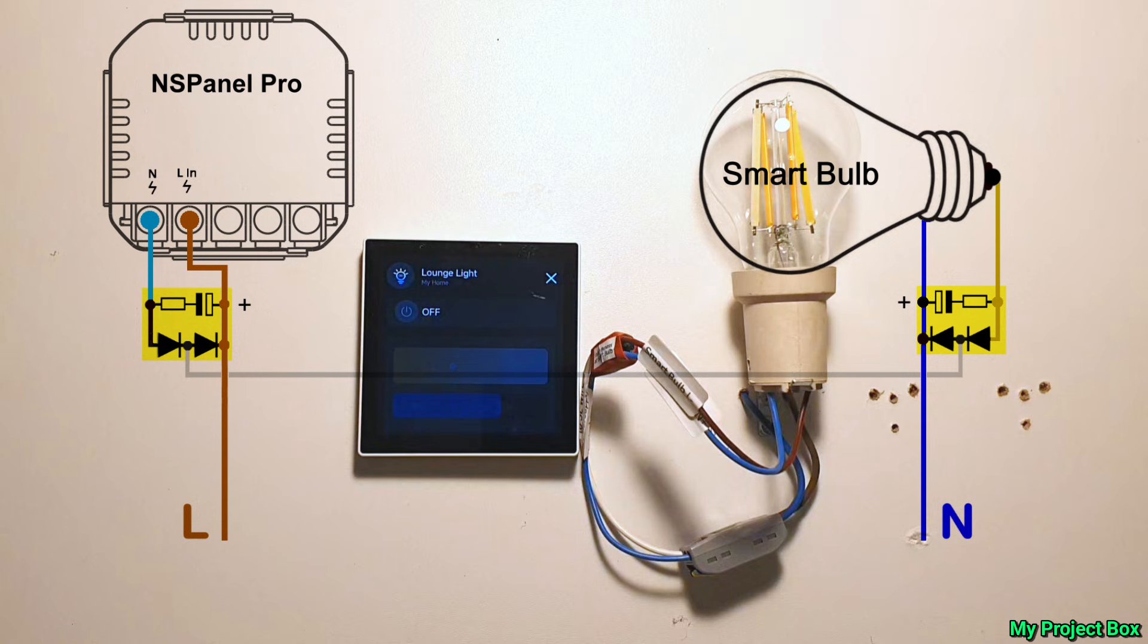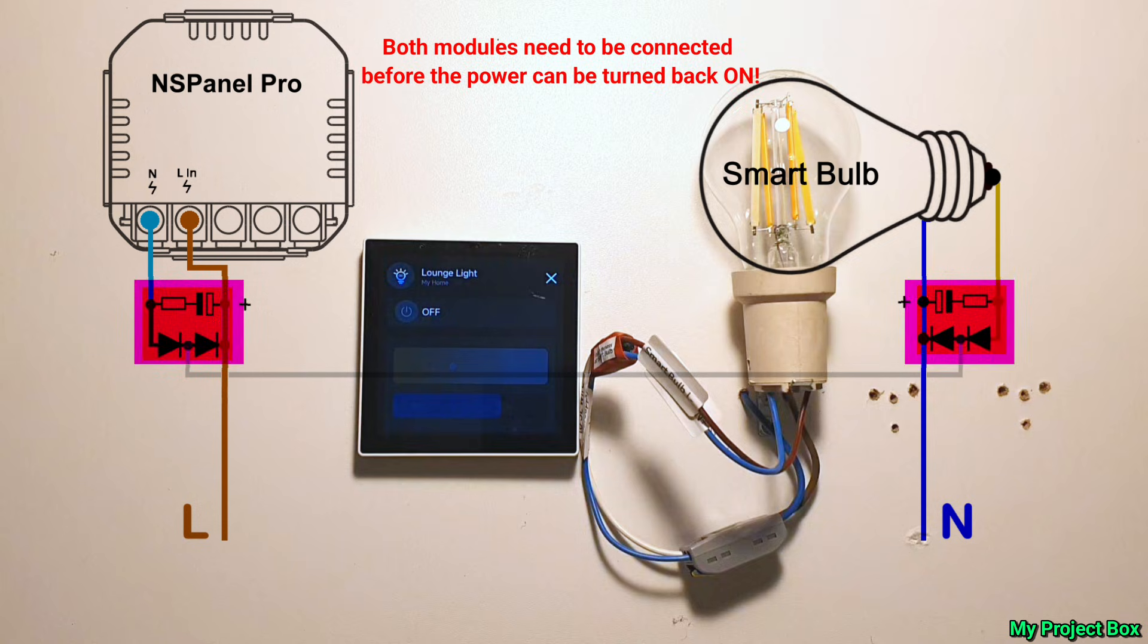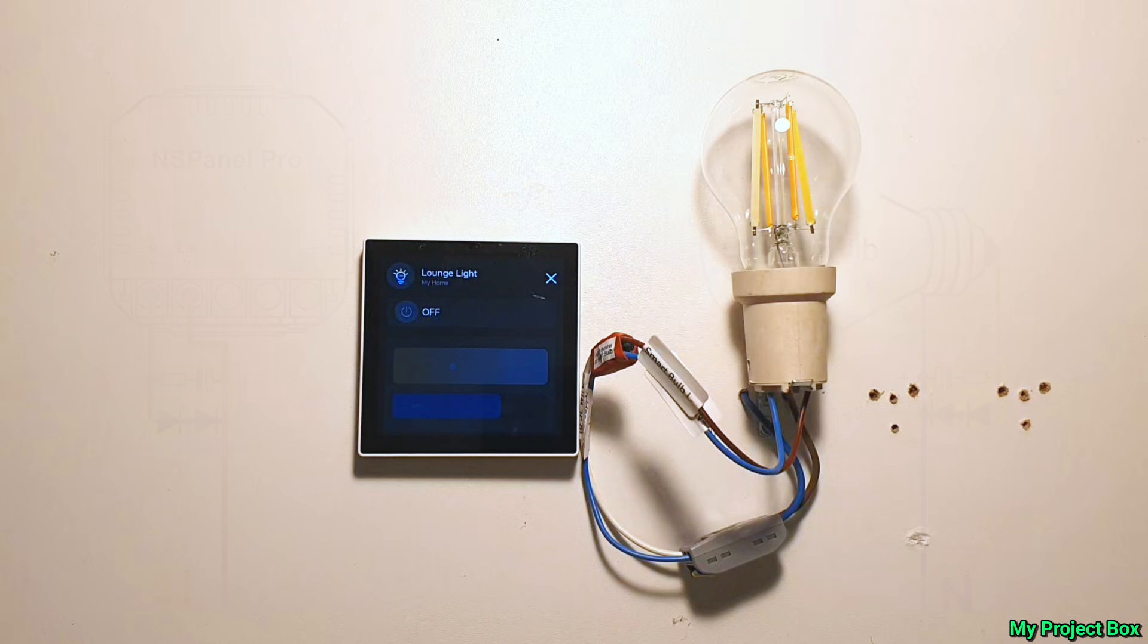Now I'd just like to mention that it's super important that both modules need to be connected first before the power is restored. If you just connected one of them at a time and then restored the power you'd have a dead short. So both have to be connected first before you restore the power.